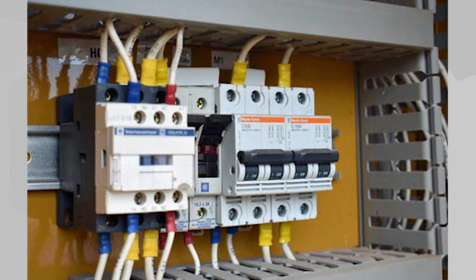Circuit breakers in themselves are safety devices because they work to cut off the power to a building when there is too much electrical current flowing through the wires. However, there are safety precautions that can be taken to prevent any electrical problem or harm to people. There is also a product that can help prevent electrocution when working with an industrial circuit breaker. All personnel working on an industrial circuit breaker should be trained in electrical circuit breaker and switch operation safety.